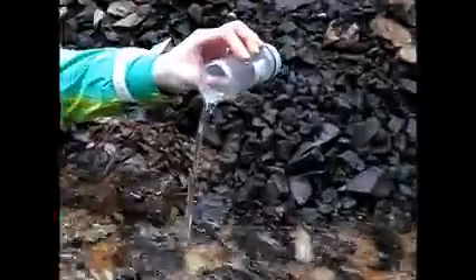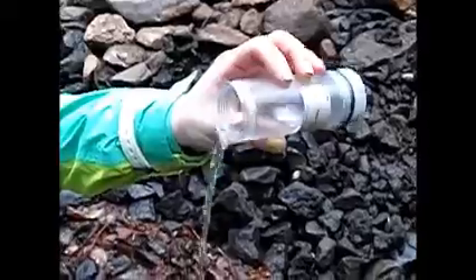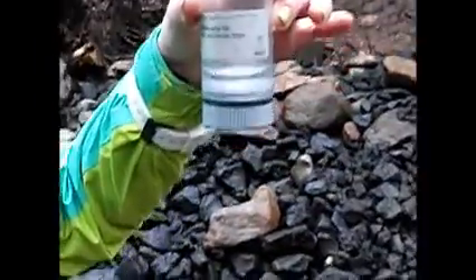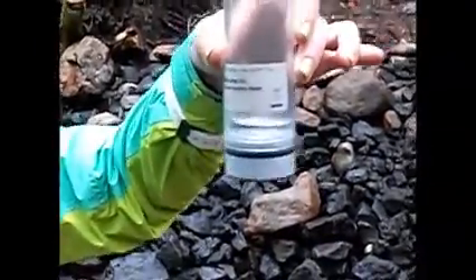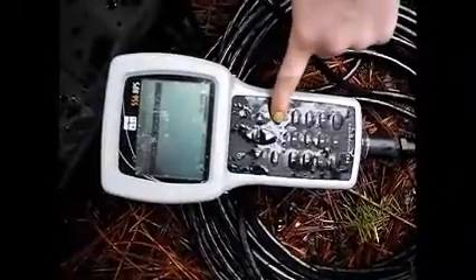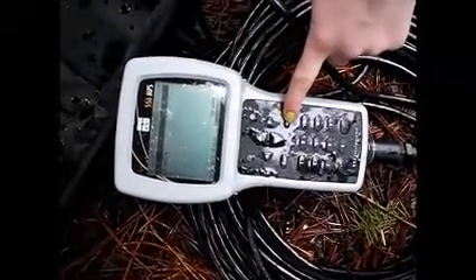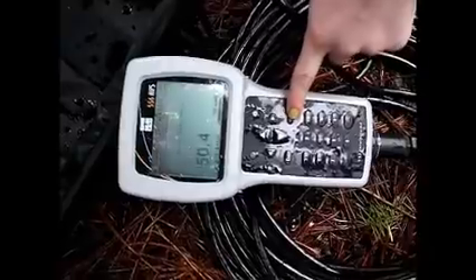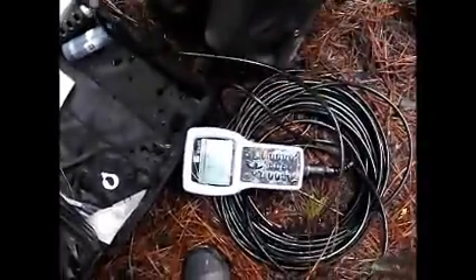Last, we'll calibrate for dissolved oxygen. This will take about 10 minutes, so get comfortable. First, you'll want about 3 millimeters of water in the bottom of the plastic cup. Then, you'll want to screw the cup onto the probe, but only engage a couple of the plastic threads. Air needs to be able to circulate and the pressure stabilize for the calibration to work. After about 10 minutes, when the readout has stabilized, accept the reading.